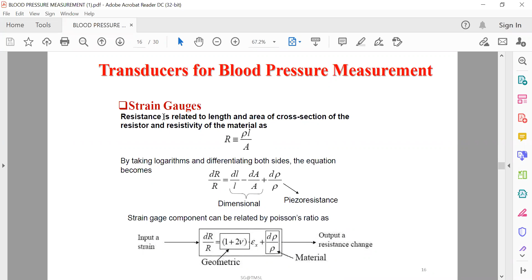Now to obtain the degree of sensitivity required for blood pressure transducers, two or four-way strain gauges are mounted on a diaphragm or membrane, and these resistances are connected to form a bridge circuit. In general, the four resistances are initially about equal when no pressure or strain is applied, and the gauges are attached to the pressure diaphragm in such a way that as the pressure increases, two of them stretch while the other two contract. In the bridge circuit, an excitation voltage is applied. So when pressure changes, it unbalances the bridge and a voltage appears between opposite terminals, which is obviously proportional to the pressure.